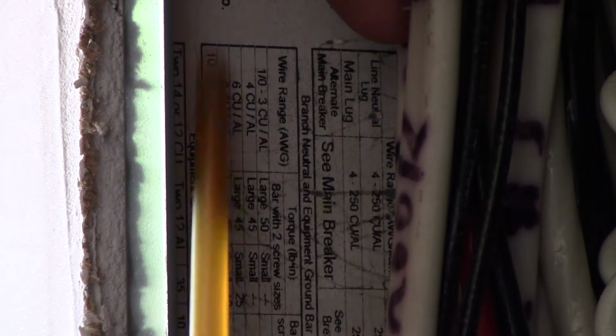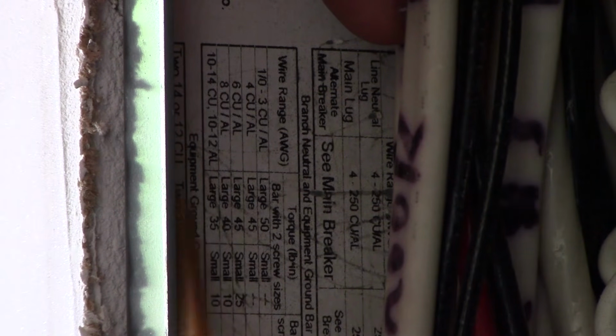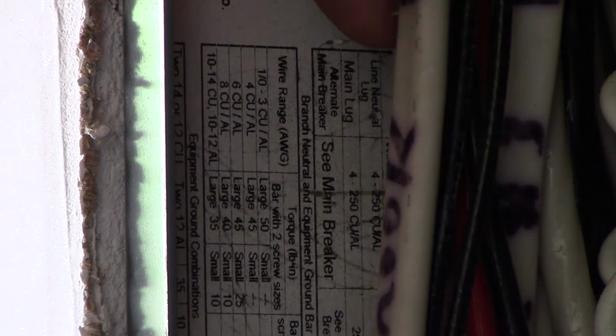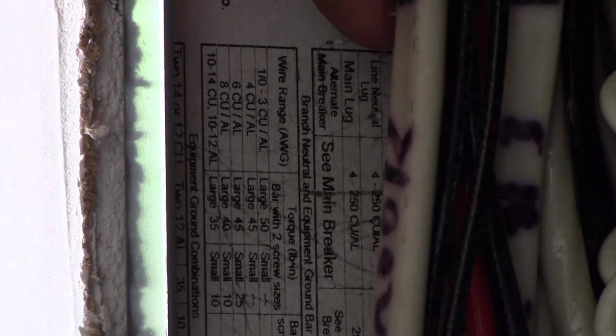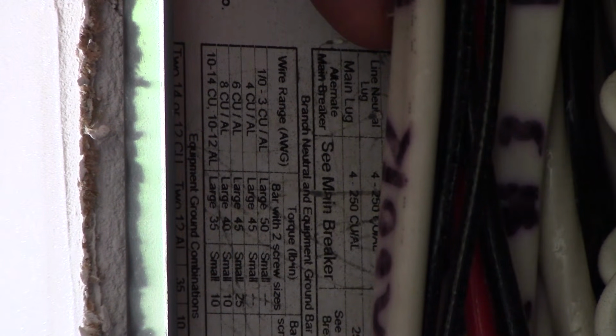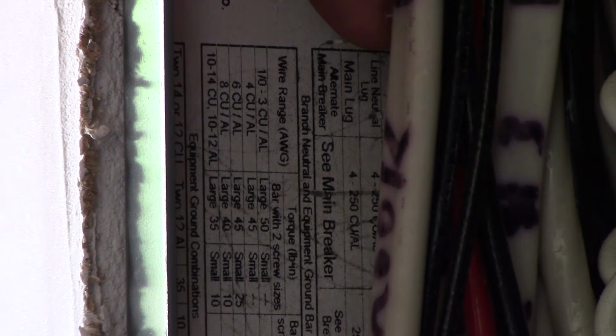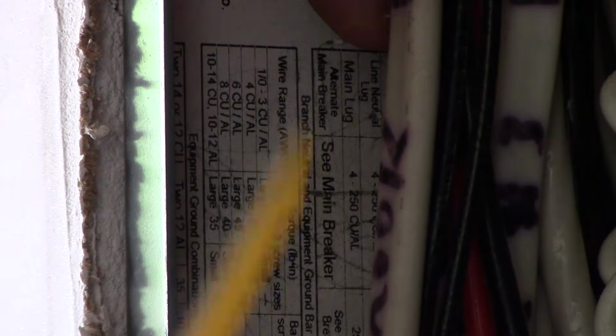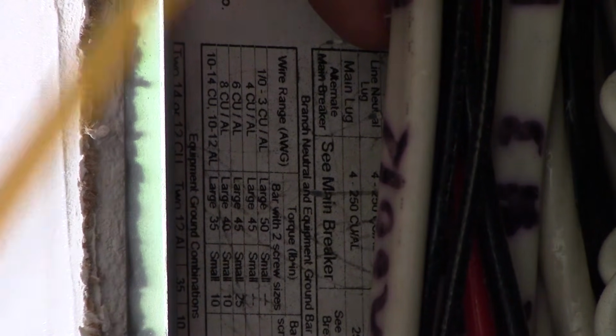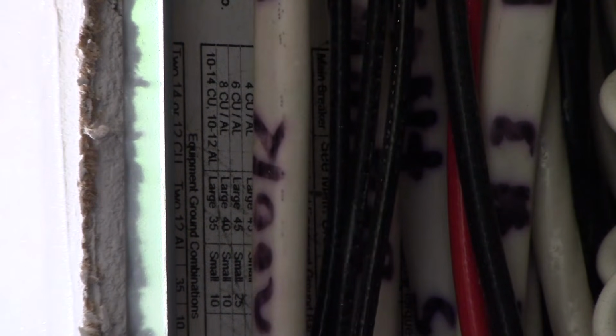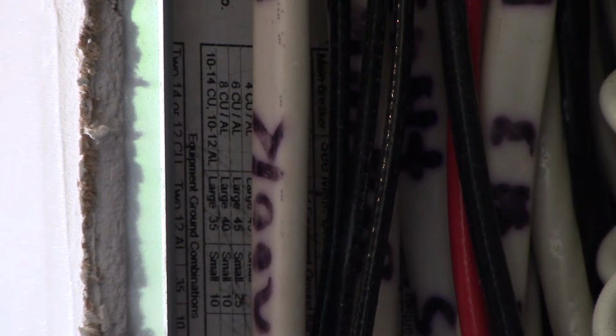So if I had aluminum conductors in here for branch circuits, they could share. But that's going to let you know. You notice that it doesn't say that for the grounded conductors, only the equipment grounding conductor. So that's part of UL 67 and the listing of this enclosure. Even if 408.41 says that you only have 1 conductor per terminal for the grounded conductor, it is also covered in this information here, and this has gone back many, many years for UL 67 and the panel manufacturers. And here you have some torquing requirements for the terminals and everything like that. It gives some guidance for the electrician who should be torquing all of these connections. So that's all that one pretty much gives you.